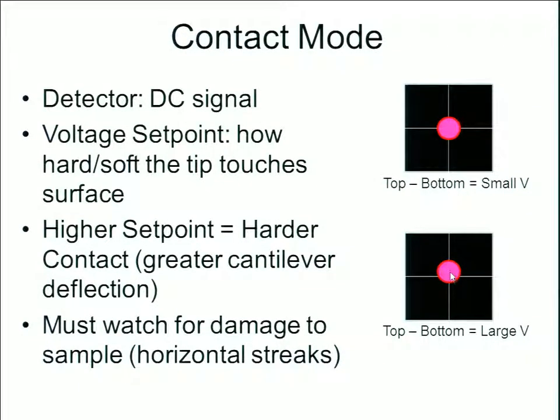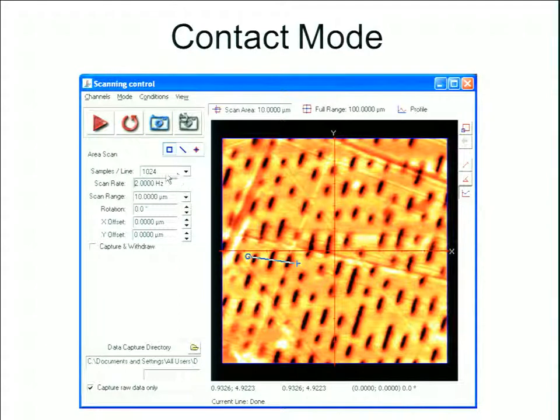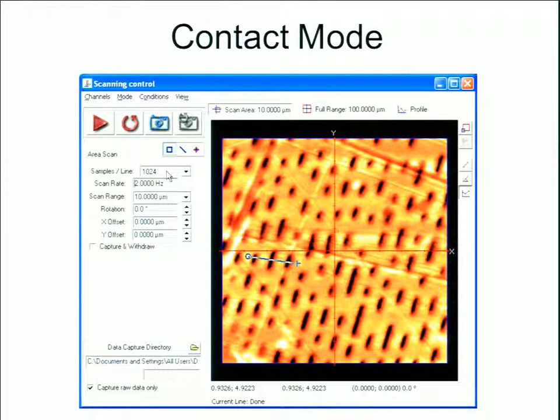Here's an image of software used to run an AFM scan. This was in contact mode. On the left we see how many data points were gathered per line — 1,024 data points. This is a 10 by 10 micron square, so that would be 1,024 times 1,024 data points — over a million data points plotted in this image.